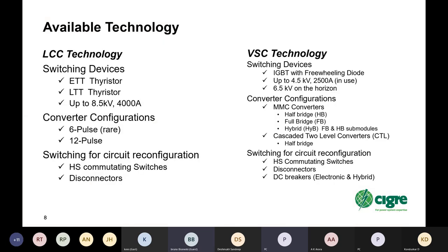So looking at available technology, and this is in two columns. On the left, you have LCC technology, switching devices available, electrically triggered thyristors, light triggered thyristors, ratings up to 8.5 kV, 4,000 amps, converter configurations, 6 pulse and 12 pulse. 6 pulse is relatively rare now, and 12 pulse is the standard now, but in the early days, 6 pulse was quite common.